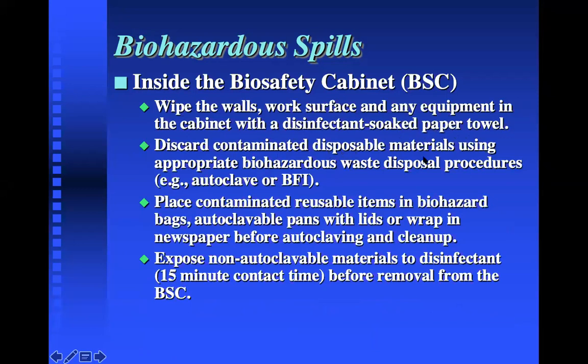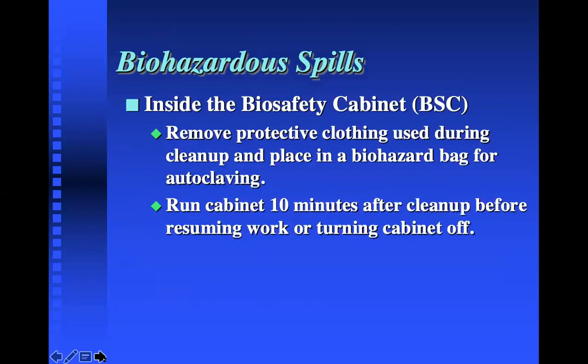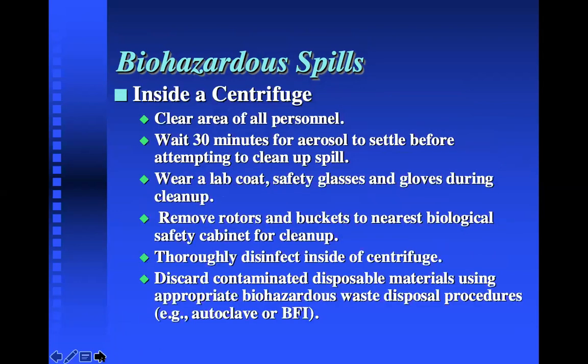Discard contaminated disposable materials using the appropriate biohazardous waste disposal procedure, for example autoclave, and place contaminated reusable items in biohazard bags. Expose non-autoclavable materials to disinfectant with 15 minutes contact time before removal from the biosafety cabinet. Remove protective clothing used during cleanup and place it in a biohazard bag for autoclaving. Run the cabinet 10 minutes after cleanup before resuming work or turning the cabinet off. This is important.